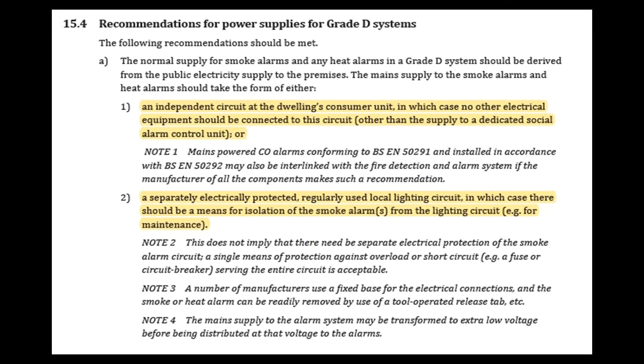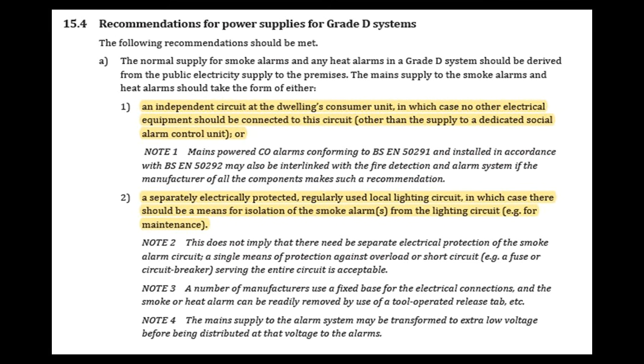15.4. Recommendations for power supplies for grade D system. A grade D is a mains smoke detector or smoke alarm system or heat detector. So we've got two options. We can either install an independent circuit at the dwelling's consumer unit, in which case no other electrical equipment should be connected to this circuit. So it's a completely independent, dedicated circuit. We've got nothing else on it whatsoever. This is what I used to do many, many years ago. We used to go into properties, do rewires, and have a dedicated circuit.